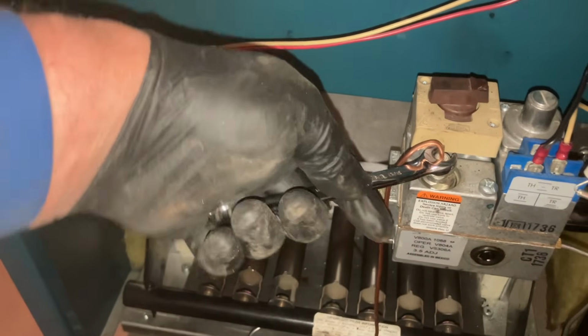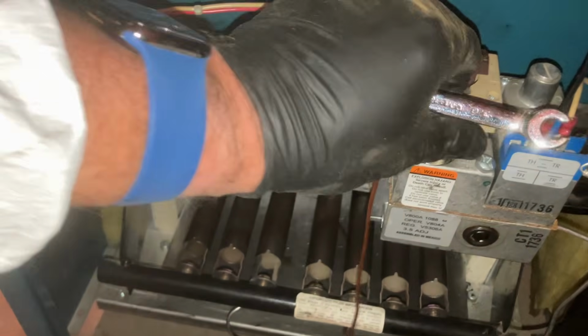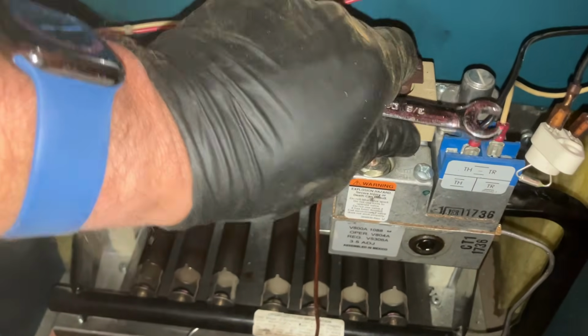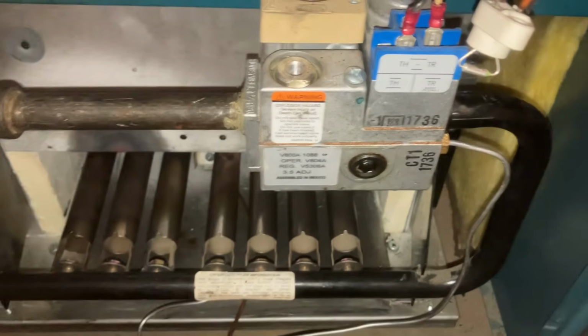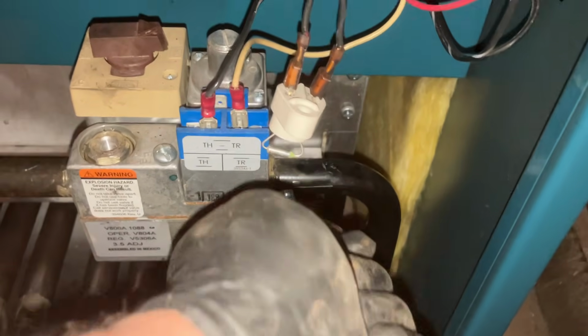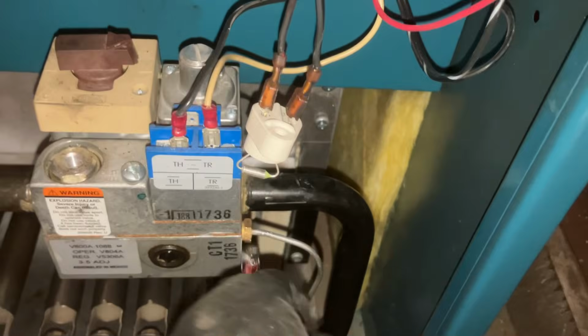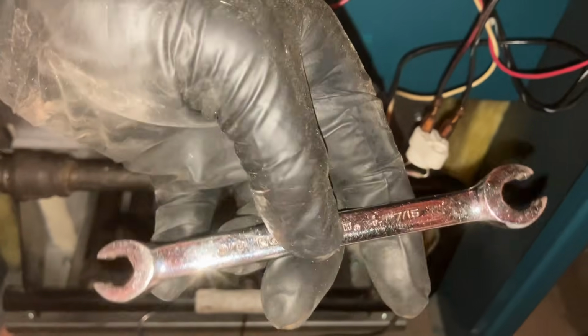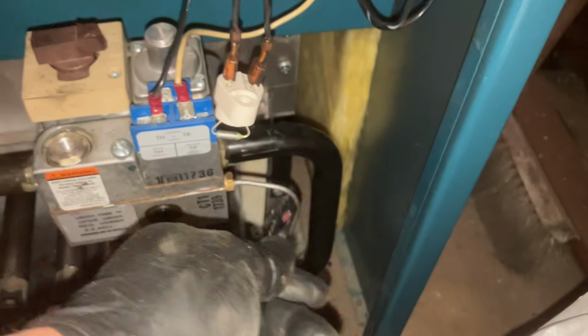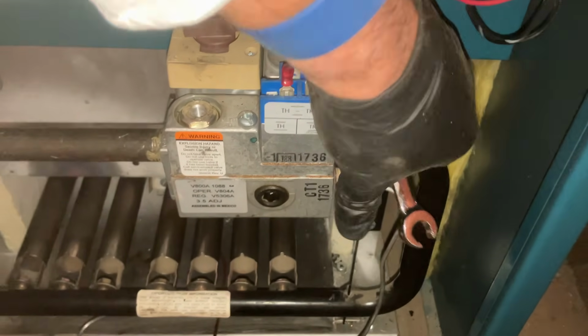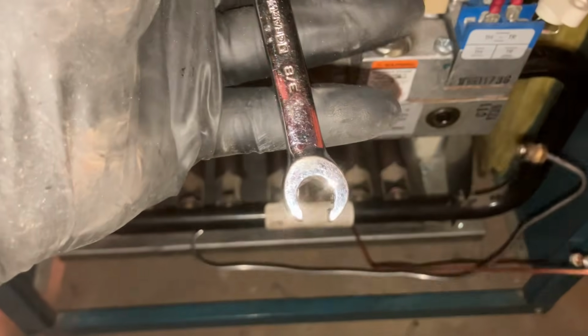All right, now that the top is out, before we start scrubbing, we need to remove the burners from the combustion chamber and the gas manifold. I'm using a 3/8 and 7/16 box wrench. If you guys work with pilot tubing, this size, the 7/16 is always the size of the nut and the ferrule, and the 3/8 is always the size of the thermocouple.